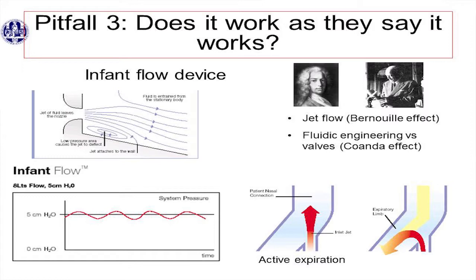And not only that: when the patient takes an inspiration, the expiratory tube is open to air, so he is allowed to pull in more air than the flow that is given. So it will give you a more stable CPAP pressure. And during expiration, that's the Coanda effect, the fluidic flip. That's what you observe if you pour tea into a cup, and there are always some drops coming from the spout. What's that?